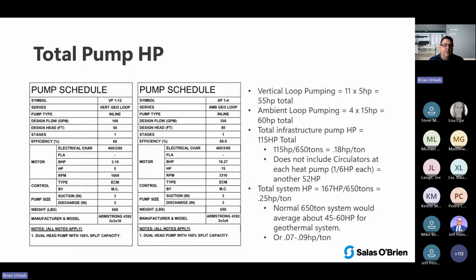And you can see here, this isn't awful for 600 tons, or 500-some tons of capacity, 650 tons of capacity. We're not that much worse than a typical building if it was of the same size. So again, just want to make a note that pump energy is critical, because this is all parasitic loss. There's no benefit to this. And so you definitely need to keep this in mind when doing your design. And then, of course, in your operation, when you turn a system on and you're going through your optimization, cutting back on your pump operation is critical. Anytime you can reduce pump speed, you want to do that.